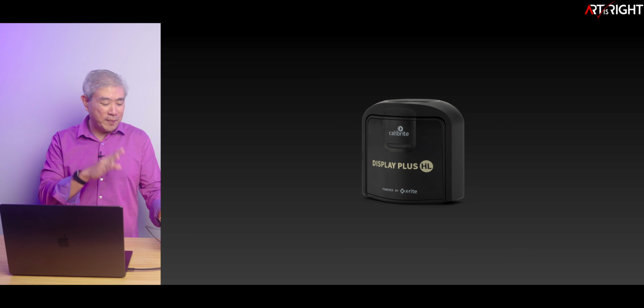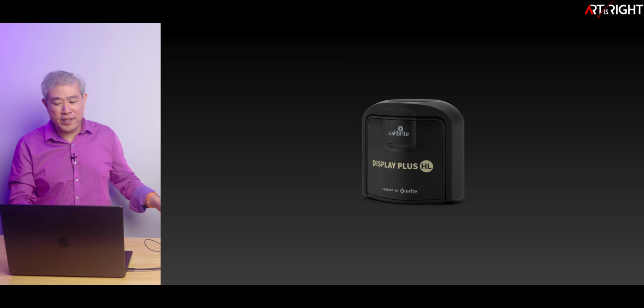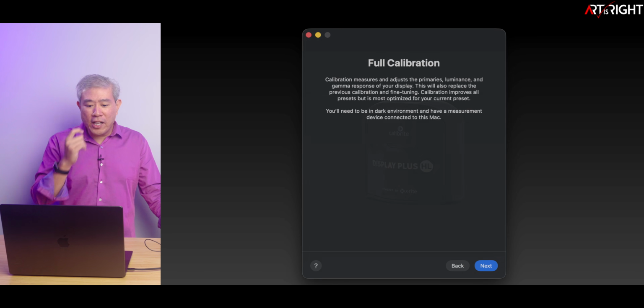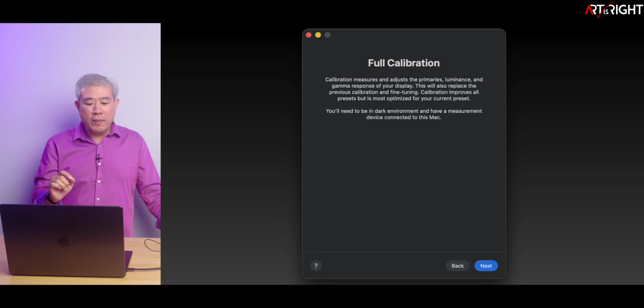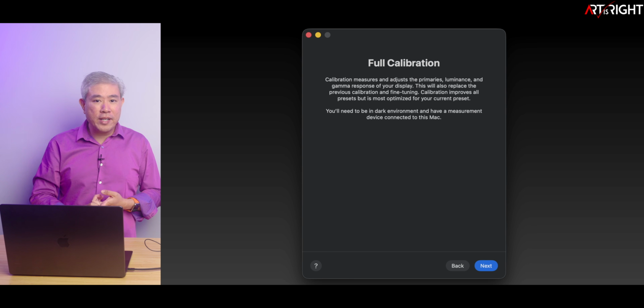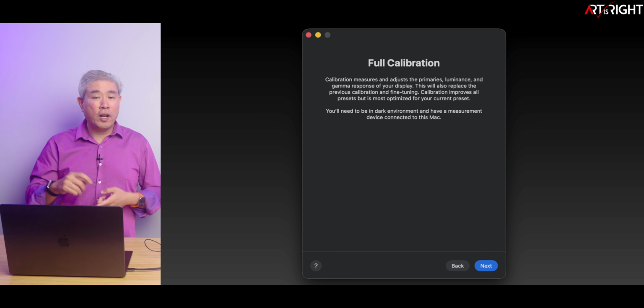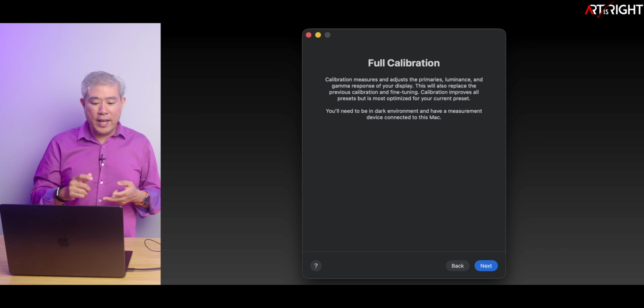HL, and this is really awesome, like I said, for so many different reasons. Now, when you do a full calibration, it's going to do the following. The calibration measures and adjusts the primaries, that is the X and Y coordinate, on the white balance or the white point of the display, the luminance, and also the gamma response of your display. It will also replace any previous calibration and fine tuning.